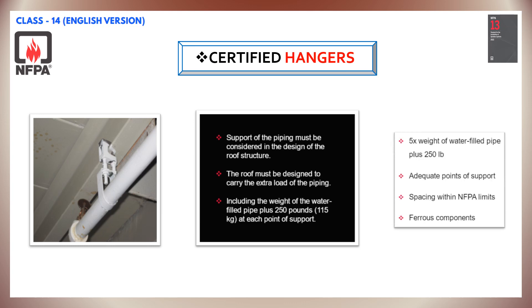Hangers shall be designed to support 5 times the weight of the water-filled pipe plus 250 pounds at each point of piping support. These points of support shall be adequate to support the system. The spacing between hangers shall not exceed the value given for the type of pipe as indicated in NFPA 13. Hanger components shall be ferrous type. Detailed calculations shall be submitted when required by the reviewing authority, showing stresses developed in hangers, piping and fittings, and safety factors allowed.